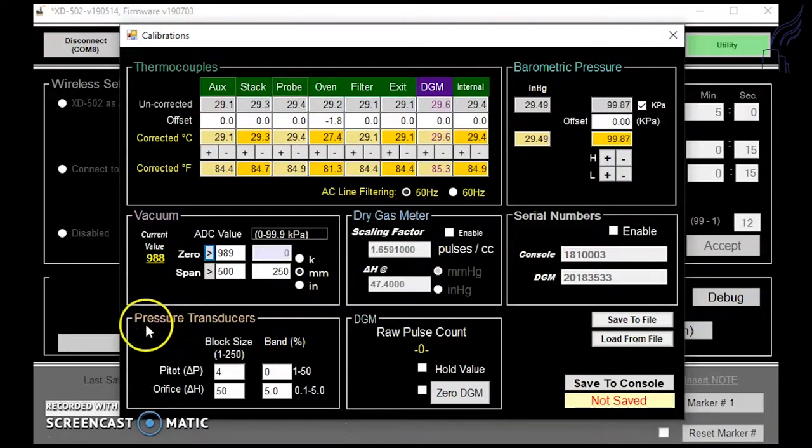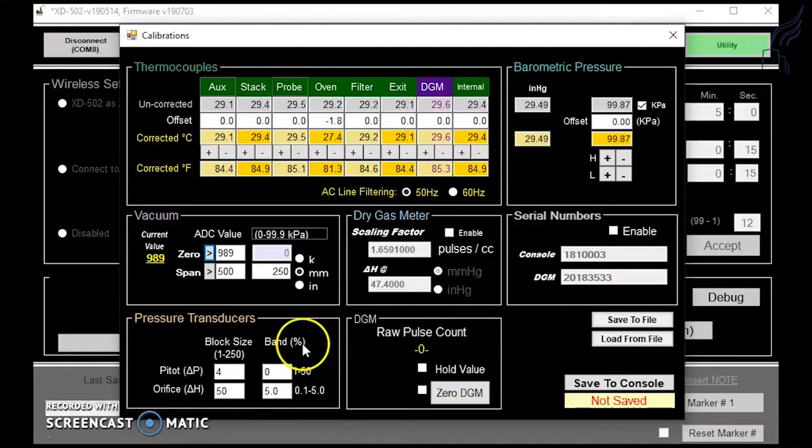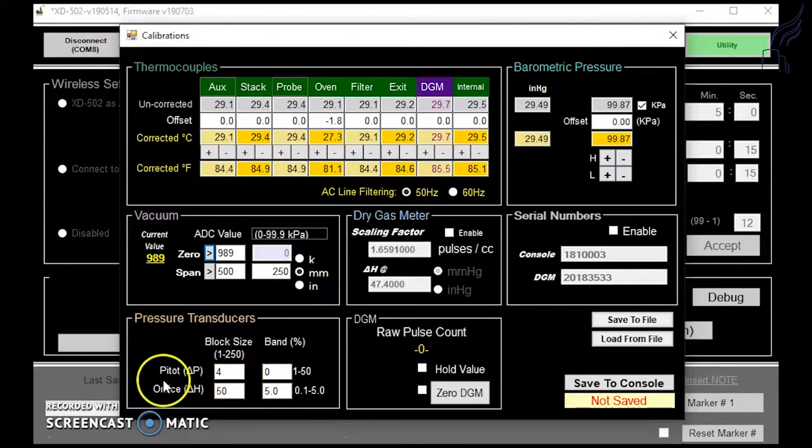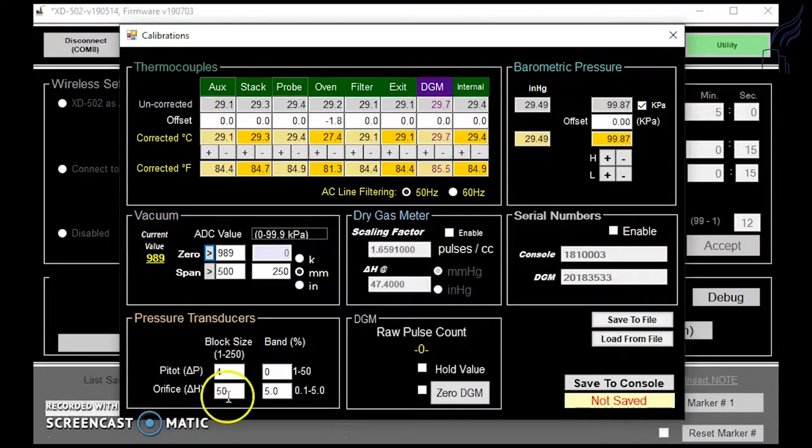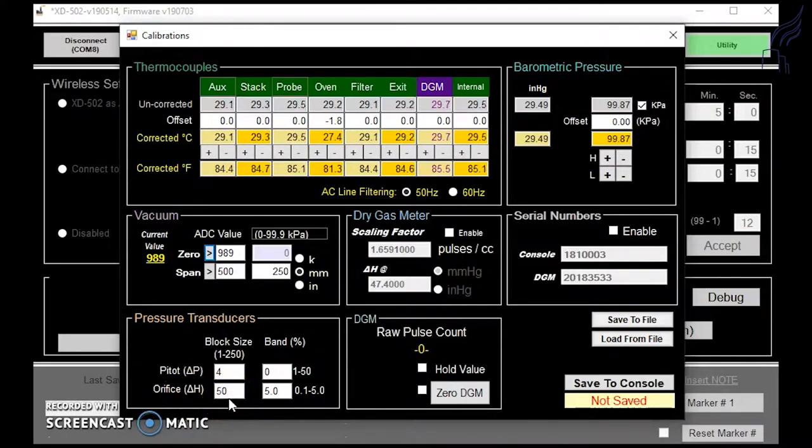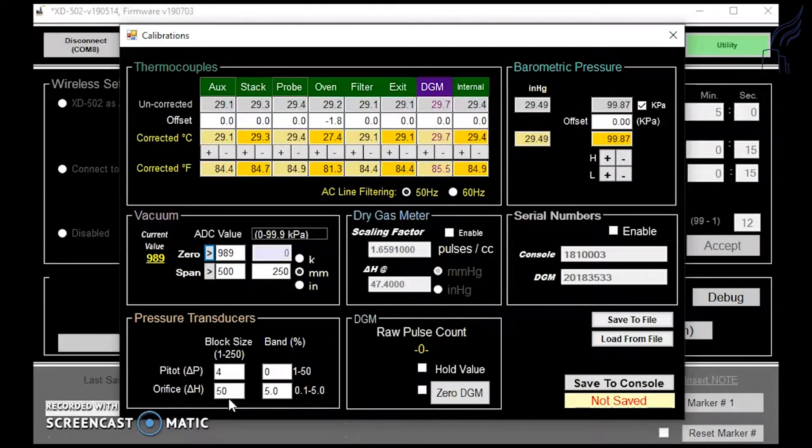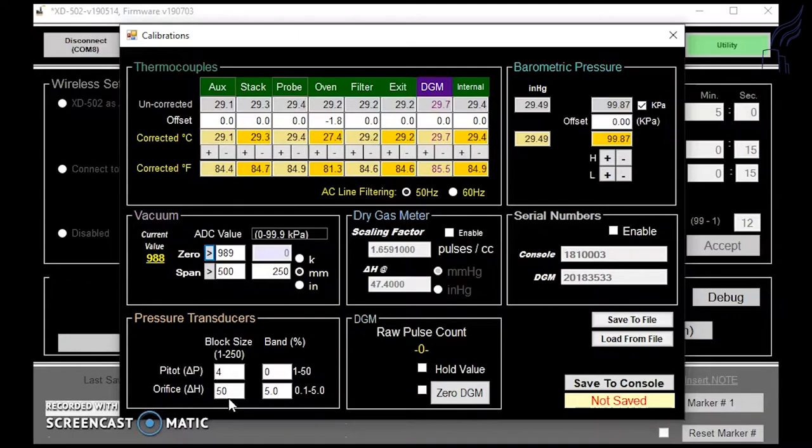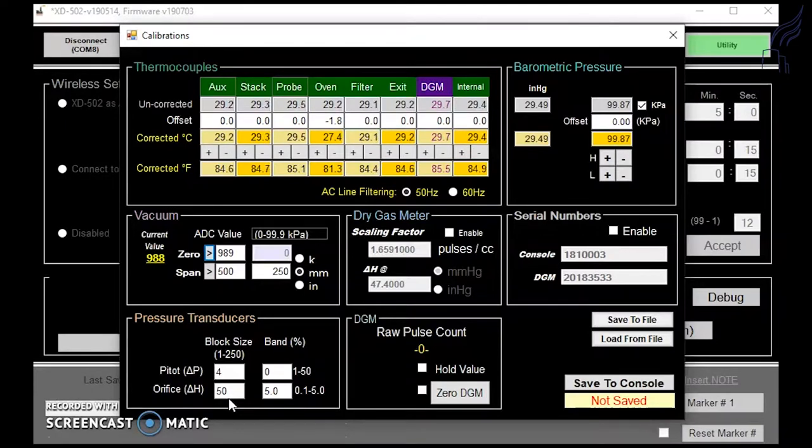For your pressure transducers, it shows your block size and your band percent. This is for both your Pitot delta P and orifice delta H readings. Block size is the number of data points that are averaged by your pressure transducers. Each block is a quarter of a second, so for example, four blocks are one second. Averaging the pressure transducers allows more stable readings on your screen of your console as well as in the software. Otherwise, the transducer may read a sporadic value that is too fast to read.